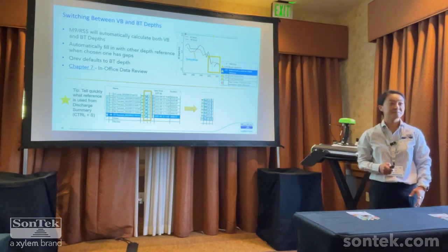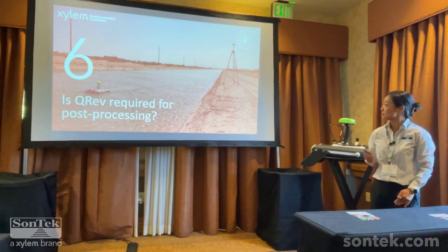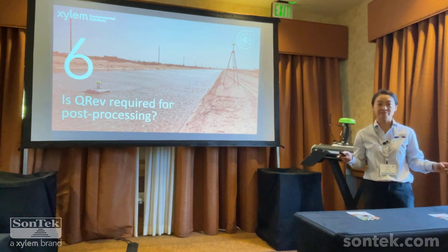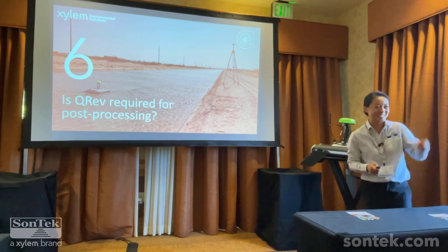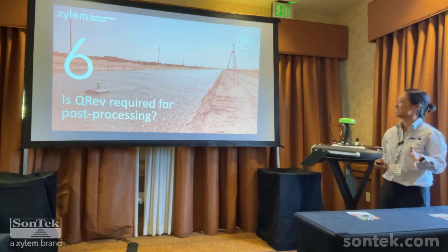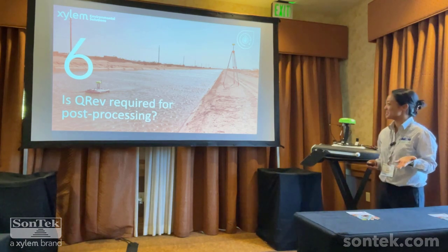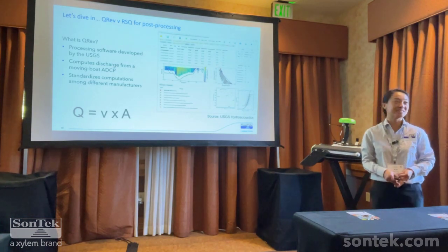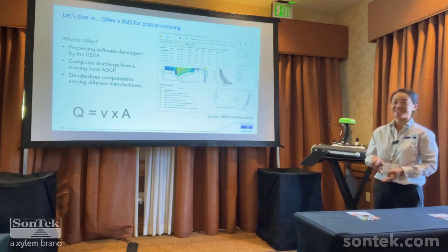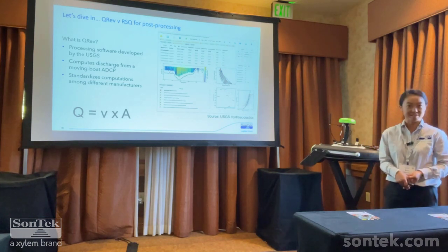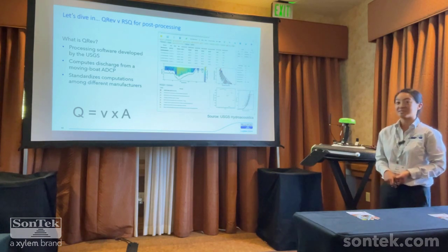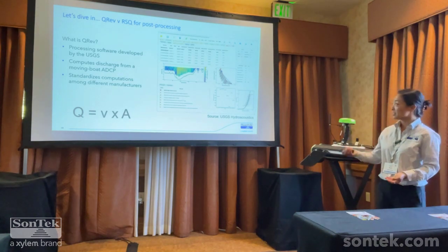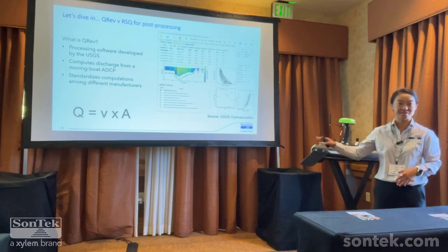Any other questions? Okay, this final topic might be a bit much for this audience, but does anybody use QRev or is familiar with QRev? Matt uses QRev. All right, so let me just mention here, in case you come across this, QRev is a tool specifically designed for the USGS. The USGS designed it and they use it in their post-processing of all ADCP measurements. And so this isn't our software, it's a USGS software, but many of our users are required to take our measurements into QRev. So that's why this topic is here.